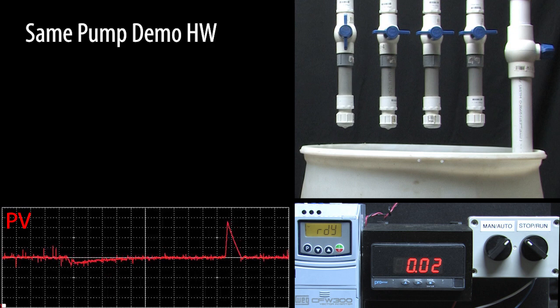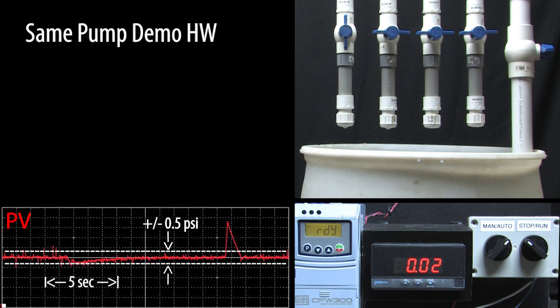Let's assume we want to maintain our pressure within plus or minus half a psi and if the pressure falls outside of that window for more than 5 seconds then we want a fault which will shut down the drive. That 5 second window will prevent these valve openings and closings from generating faults and shutting down the drive. I'm keeping these durations short just to expedite the video. What you use for your durations will depend on your system.